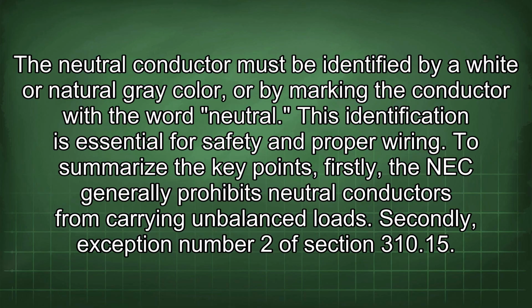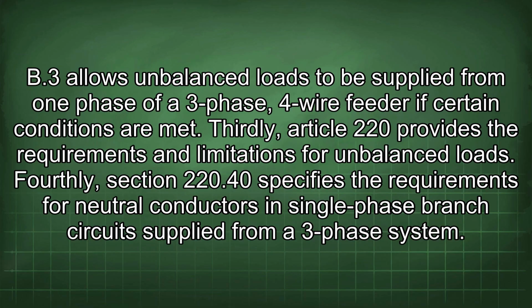To summarize the key points, firstly, the NEC generally prohibits neutral conductors from carrying unbalanced loads. Secondly, exception number 2 of section 310.15 B3 allows unbalanced loads to be supplied from one phase of a 3-phase, 4-wire feeder if certain conditions are met. Thirdly, Article 220 provides the requirements and limitations for unbalanced loads. Fourthly, Section 220.40 specifies the requirements for neutral conductors in single-phase branch circuits supplied from a 3-phase system.